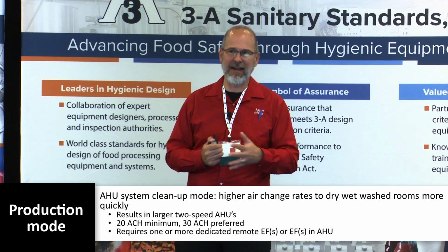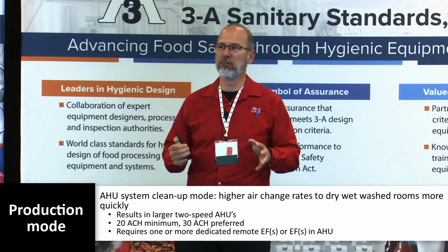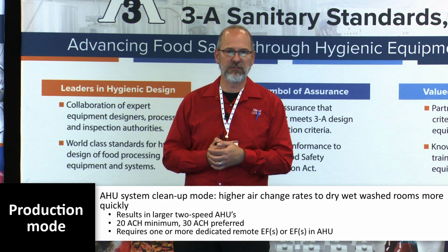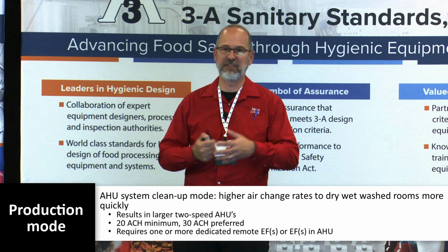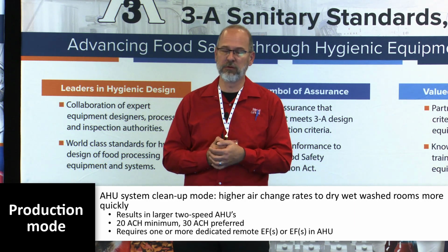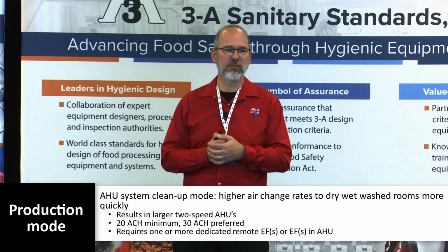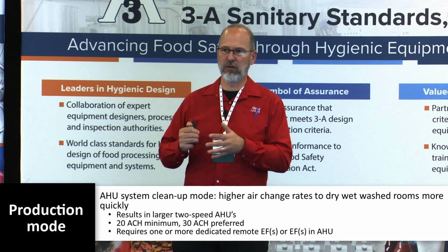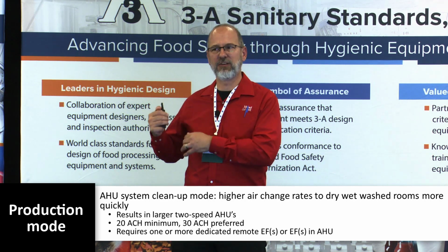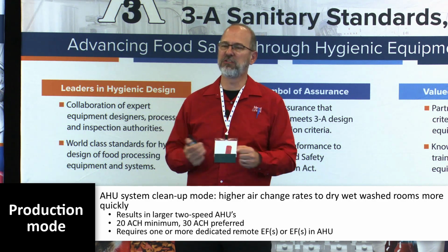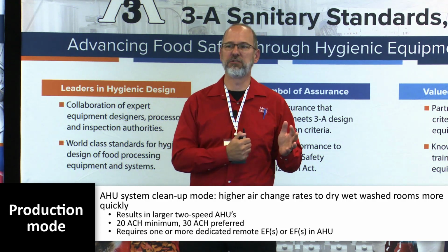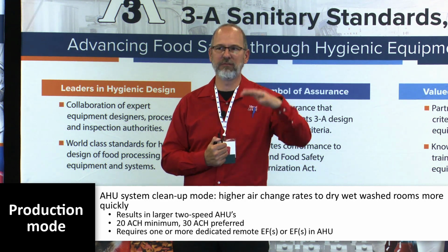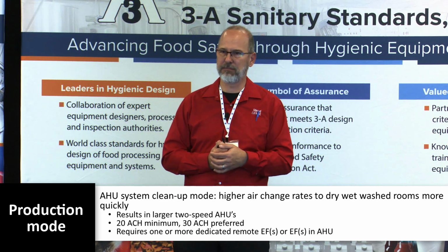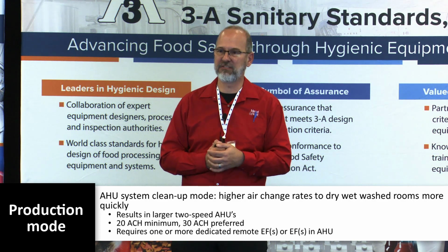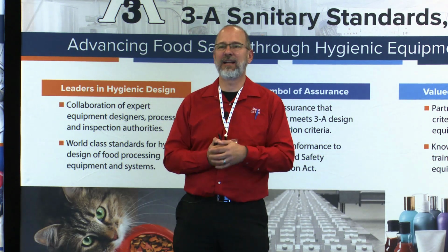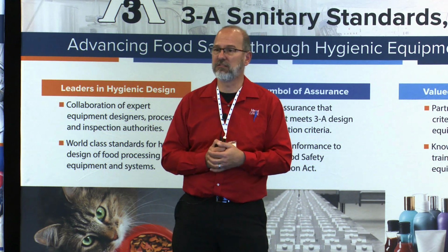And that's typically when you're not in production and you just want to purge the room. You're hosing it down, you're washing it down, you're generating a lot of moisture. Sometimes the room might be fogging if it's cool in the room. You just want to purge. So usually what will happen is that air handler will go to 100% outside air and it'll speed up and push as much air through that room as possible just to get rid of the moisture. The temperature in the room might float. You won't be trying to maintain an exact temperature or humidity in the room. You're just trying to purge the room as fast as you can. So these units can be designed to switch back and forth between those modes fairly easily.